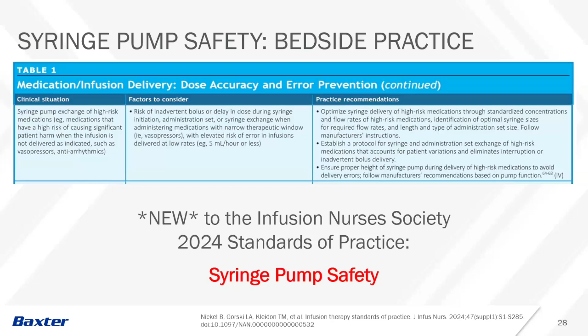Bedside practice can have a far more significant impact on drug delivery at low infusion rates. As mentioned on the last slide, syringe selection is a key factor contributing to safe drug delivery via a syringe pump. So, not all brands of syringes are manufactured alike. Using syringes identified as compatible by the pump manufacturer is key to reducing the risk of inaccurate drug delivery.